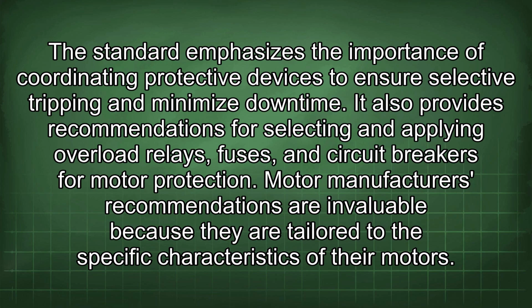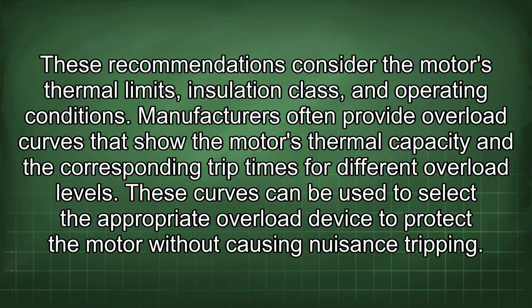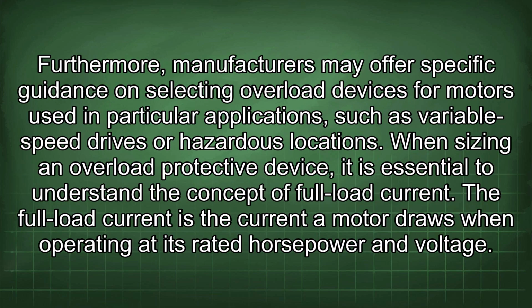Motor manufacturers' recommendations are invaluable because they are tailored to the specific characteristics of their motors. These recommendations consider the motor's thermal limits, insulation class, and operating conditions. Manufacturers often provide overload curves that show the motor's thermal capacity and the corresponding trip times for different overload levels. These curves can be used to select the appropriate overload device to protect the motor without causing nuisance tripping. Furthermore, manufacturers may offer specific guidance on selecting overload devices for motors used in particular applications, such as variable speed drives or hazardous locations.